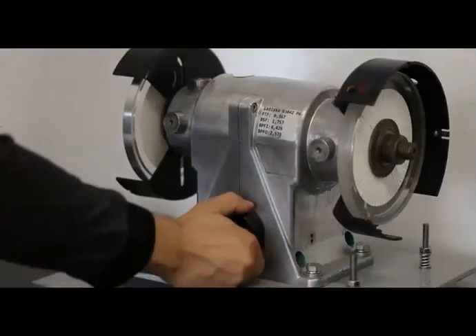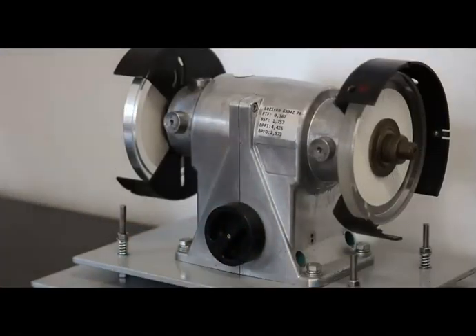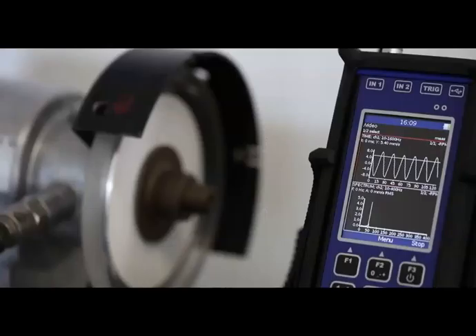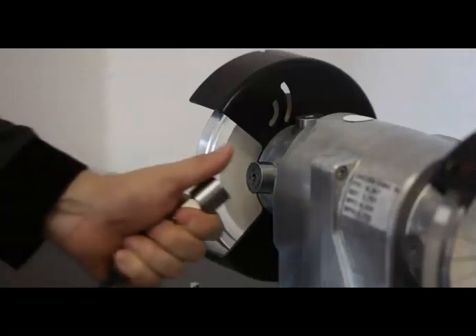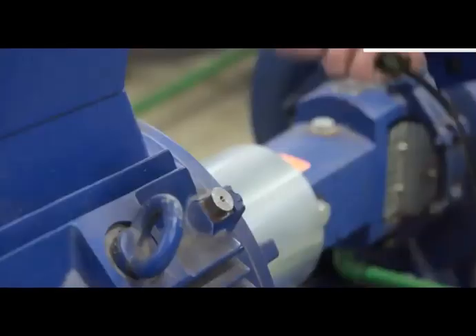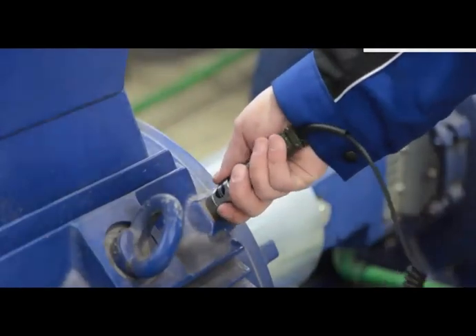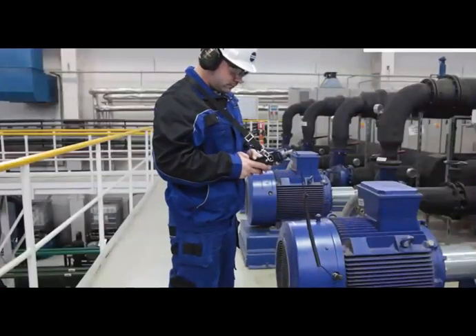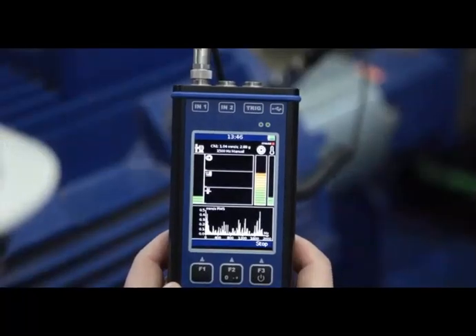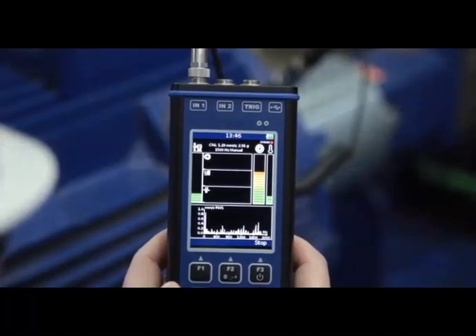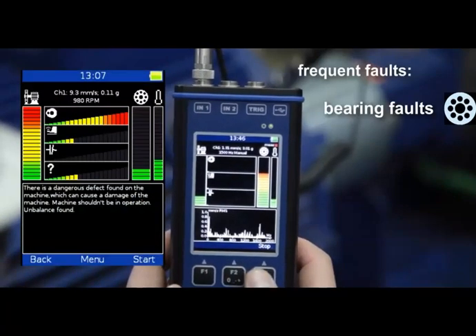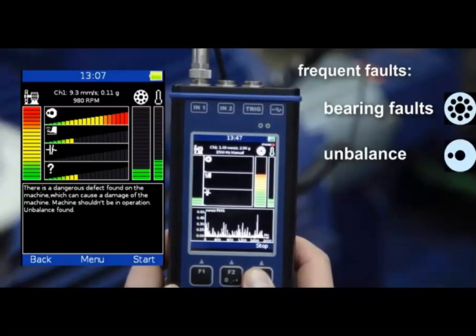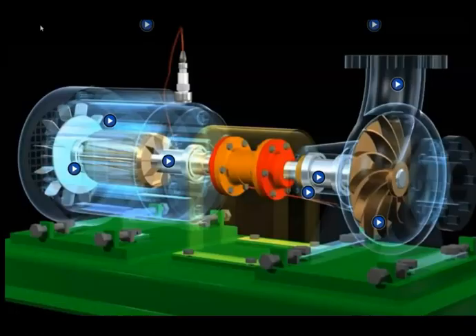How does it work? Running machines generate vibrations which contain a lot of information about their condition. A vibration meter or analyser is used to measure this vibration. The sensor needs to be mounted on an appropriate point on the machine, e.g. bearing housing. The instrument measures the vibration signal, tells you the severity of the vibrations and also possible machine faults. The most frequent faults are bearing faults, unbalance, misalignment, and looseness.